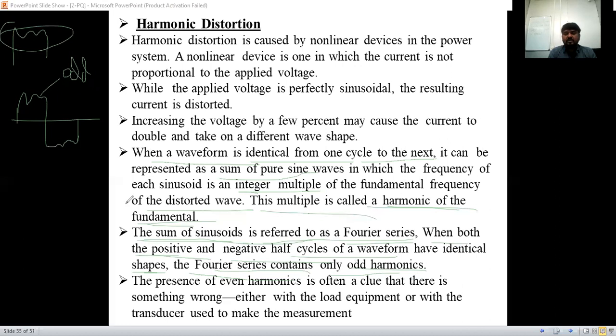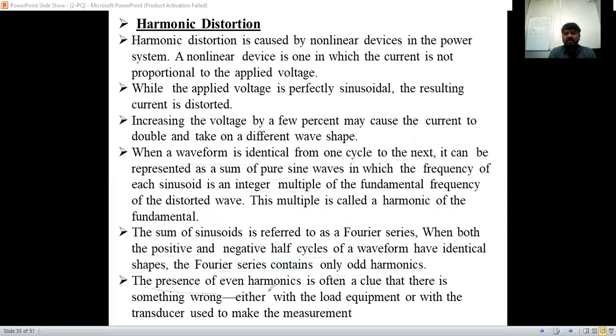If even harmonics are present, that is often a clue that something is wrong, either with the load equipment or with the transducer used to make the measurement. Transducers convert a physical quantity into an electrical quantity. So the presence of even harmonics indicates an issue with the load equipment.